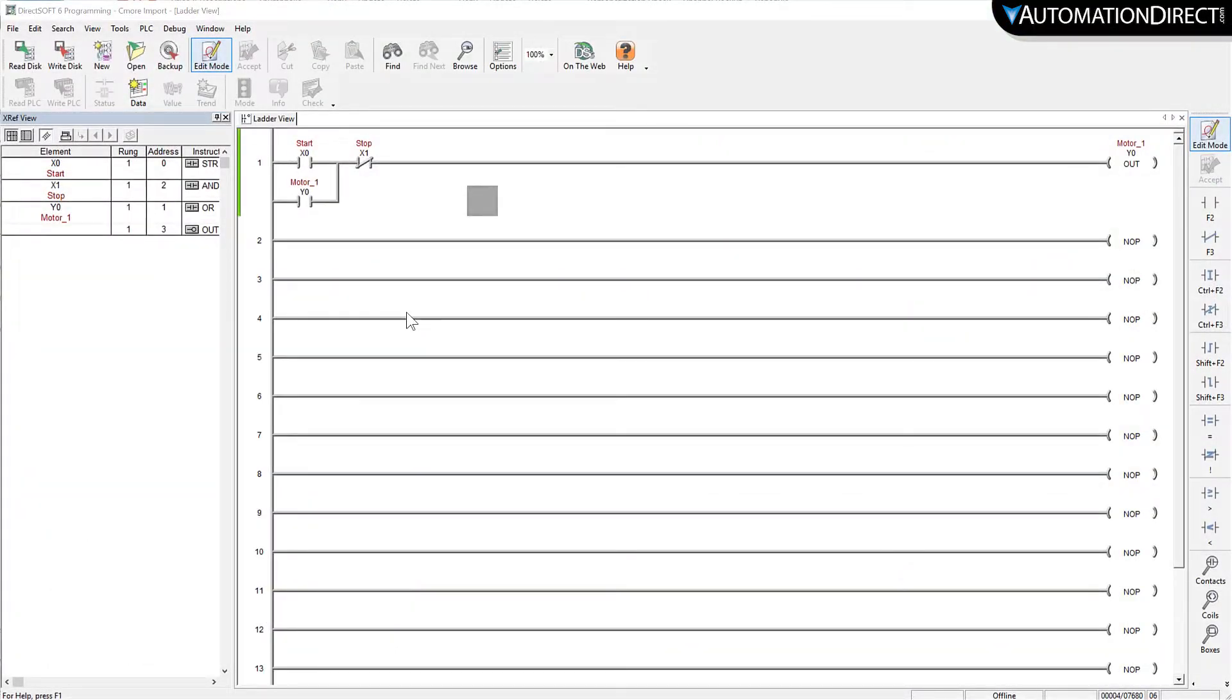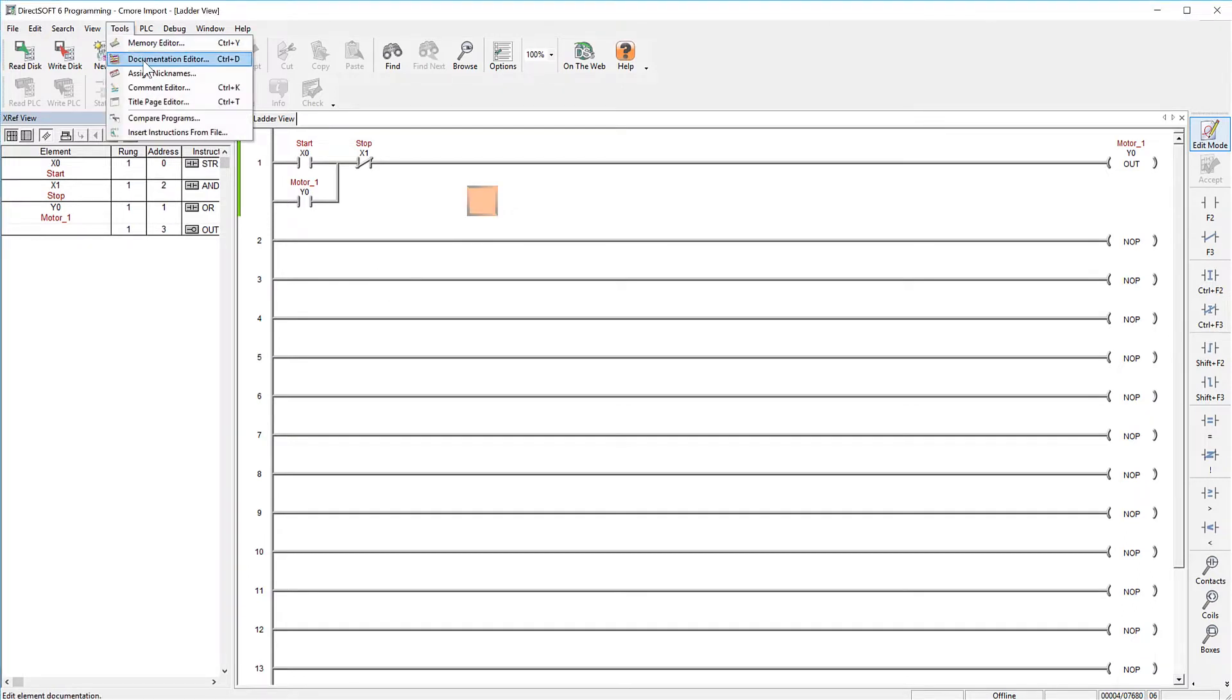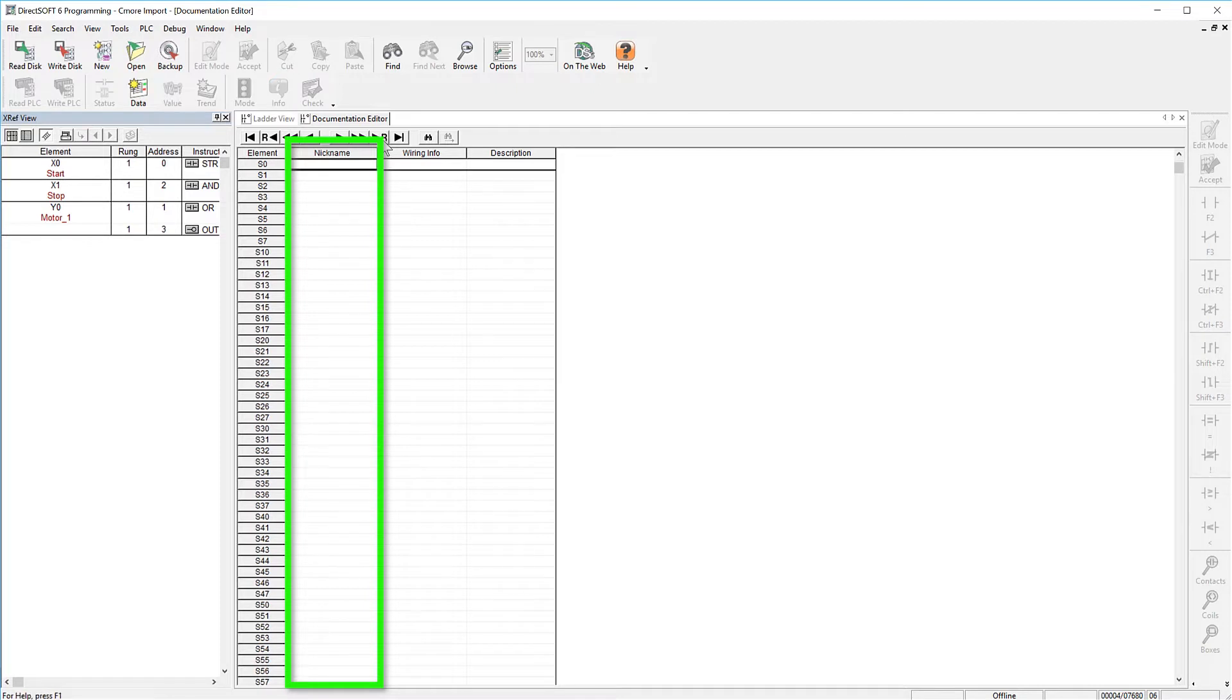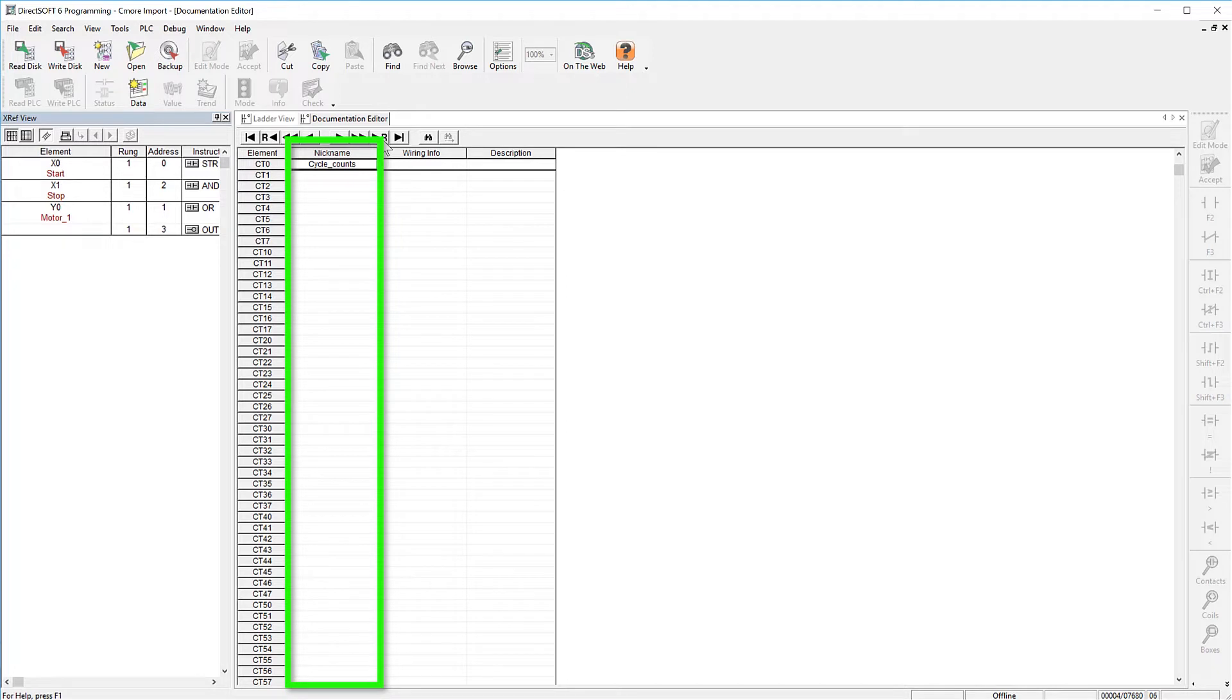Now there is a caveat to this tag import. Only the addressing that has nicknames placed here will be exported in this process. So if you want these addresses to export to your C-more HMI, you will need to place nicknames for them here.